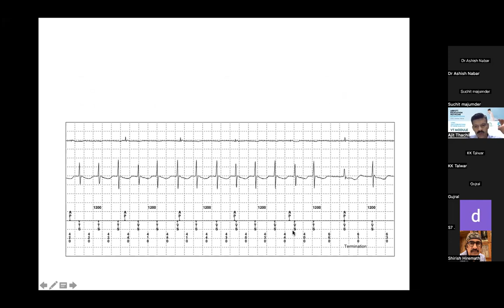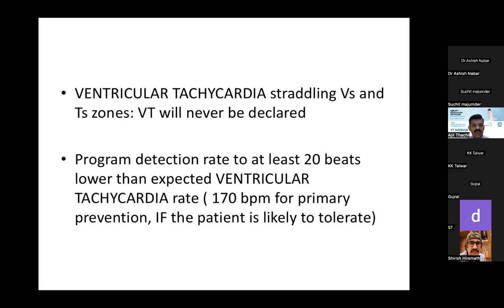So finally, the tachycardia terminated here. This tachycardia actually went on for 1 hour. So the lesson here is that with a ventricular tachycardia straddling the VS and the TS zones, VT will never be declared. So program a detection rate at least 20 beats lower than the ventricular tachycardia rate in secondary prevention. If you know the rate of the clinical VT, program at least 20 beats lower than the clinical VT.